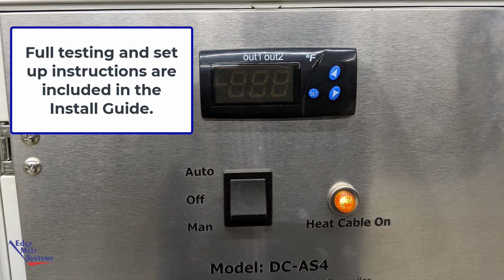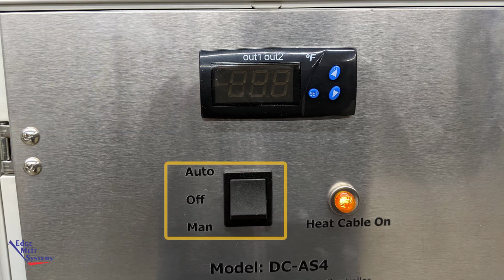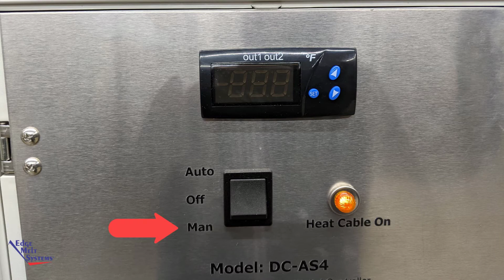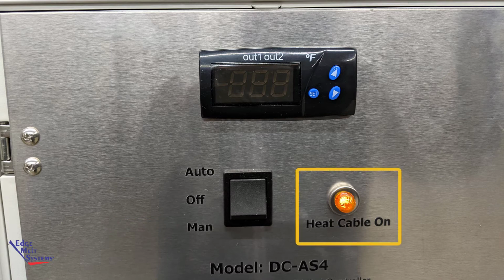For the initial setup, testing, and determining whether or not you've done everything correctly, depress the 3-position rocker switch to the manual position, and you'll see the temperature display will not light up. However, the heat cable on indicator light will illuminate, indicating that power is being sent to the heat cables.